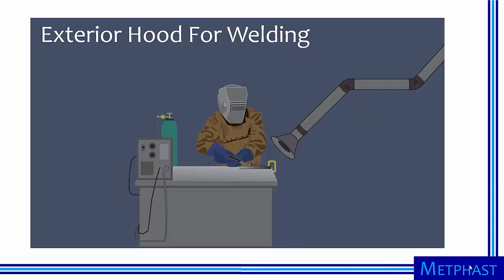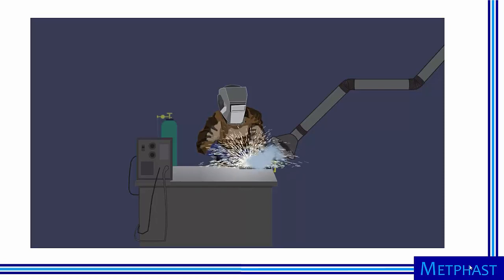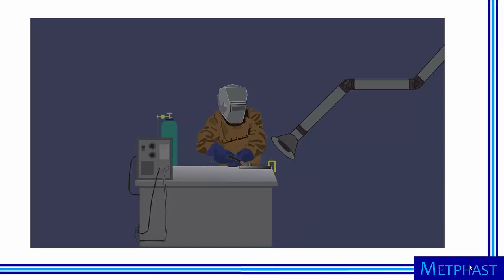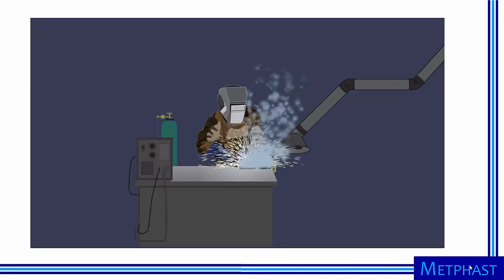This welder is using an exterior hood to capture fumes and gases emitted by welding. The hood must be placed in the proper position so that the air at the contaminant source entrains the fumes and gases, pulling them into the ventilation system. Capture is most effective when the hood is positioned close to and angled to face the source. If the hood is not angled toward the fumes source, capture will be poor regardless of proximity because air velocity is insufficient to entrain the contaminant.